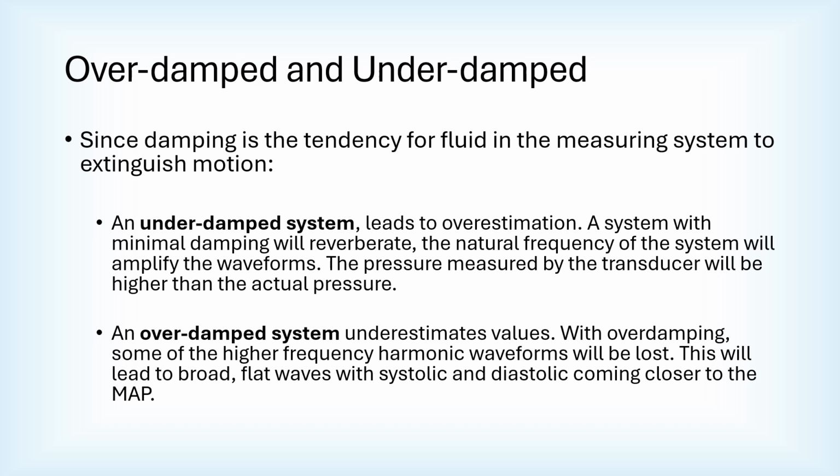An overdamped system underestimates values. With overdamping, some of the higher frequency harmonic waveforms will be lost. This will lead to broad flat waves with systolic and diastolic coming closer to the mean arterial pressure.